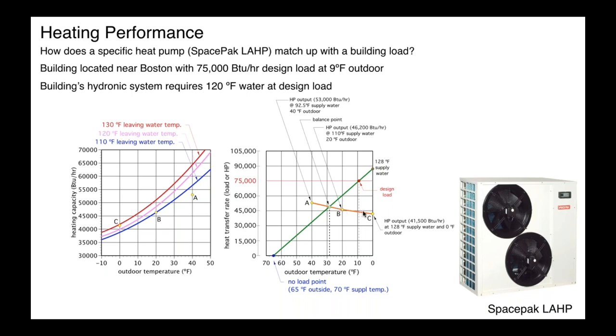And basically the orange line would represent my output from the heat pump in BTUs per hour. The green line represents the load, and they cross at about 28 degrees outdoor temperature. So the balance point in this particular application, the heat pump can supply all the building's heating requirement down to 28 degree outdoor temperature. Now, what happens when it gets colder?